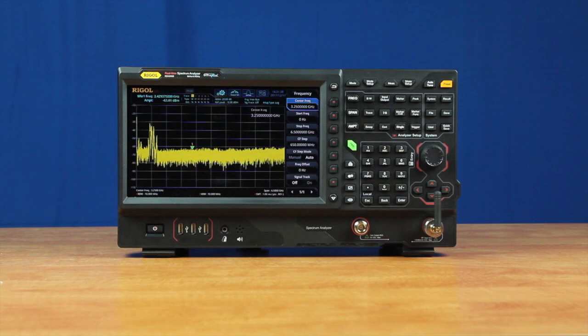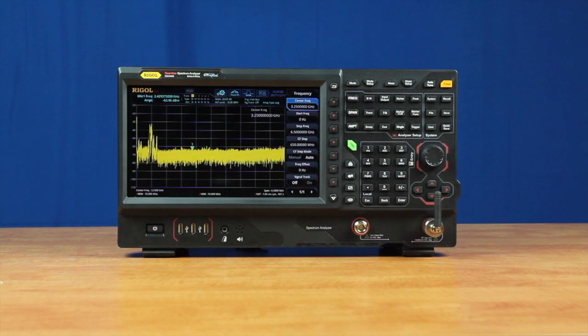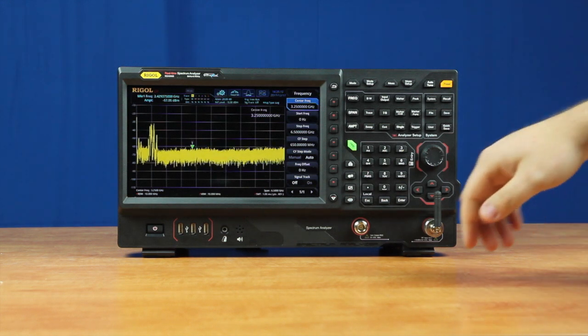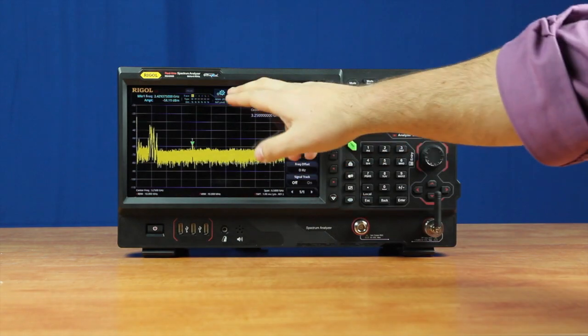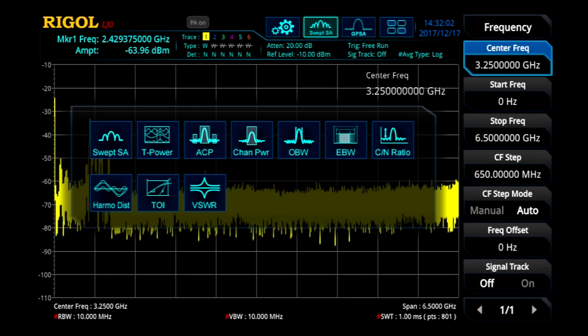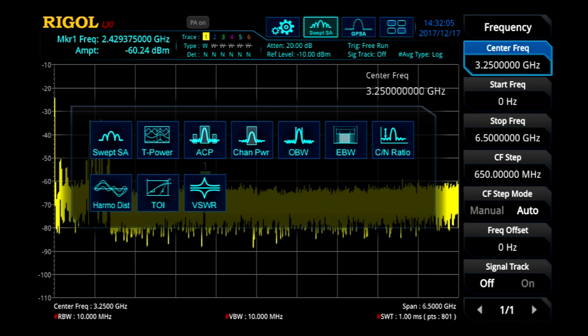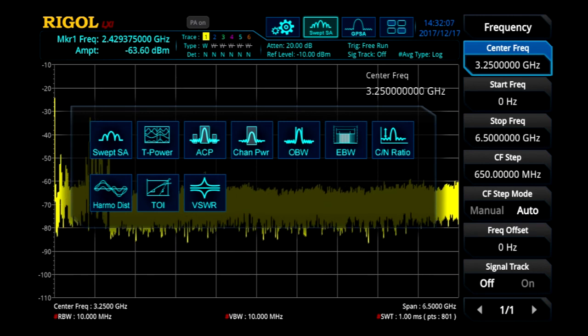In this mode, the instrument can sweep the entire frequency range for this model in one millisecond. This instrument comes with 1 Hz RBW and a noise floor of negative 165 dBm. In sweep mode, we can do more traditional RF characterization testing, including VSWR testing, harmonic distortion, channel power, and total power.